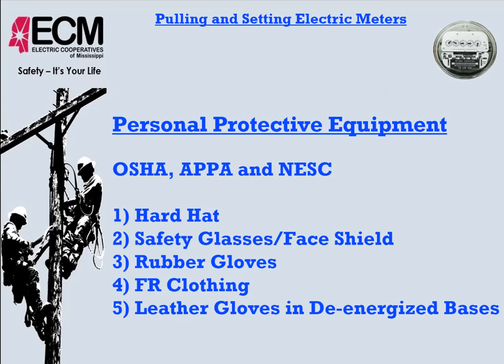And then rubber gloves. There again, I've already said it once, rubber gloves should be worn while setting and removing meters in energized condition if you choose to do that. And then FR arc rated clothes, you probably already have those on. Shirt sleeves rolled down and buttoned, your shirt's buttoned up, not all the way to the collar, but buttoned up all the way to, I guess, one hole down from the top. And then if you're working in de-energized condition, leather gloves. Pretty much everything that we do, we should have some type of hand protection regardless of what we're doing.